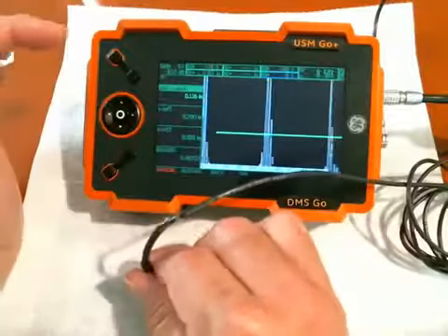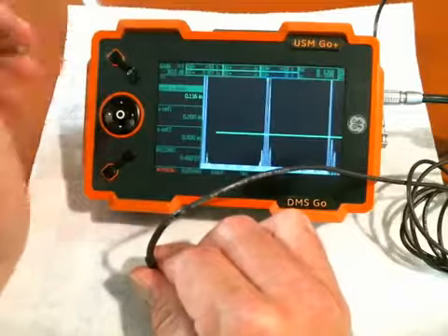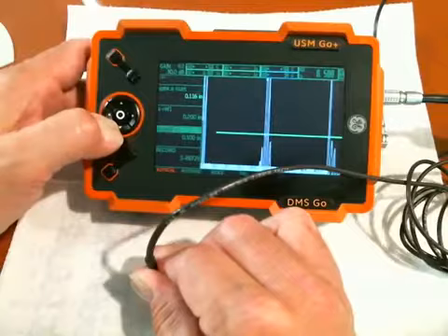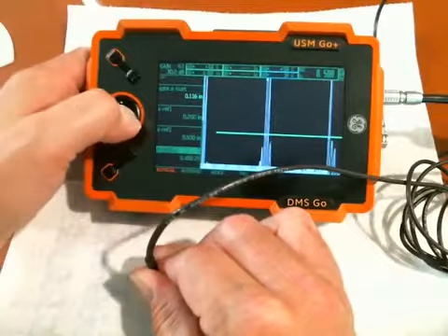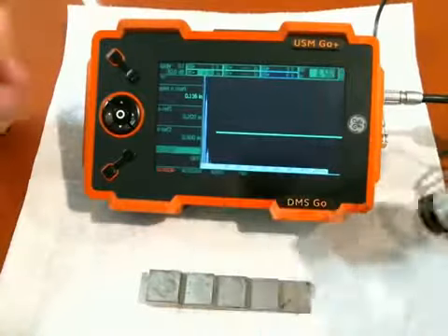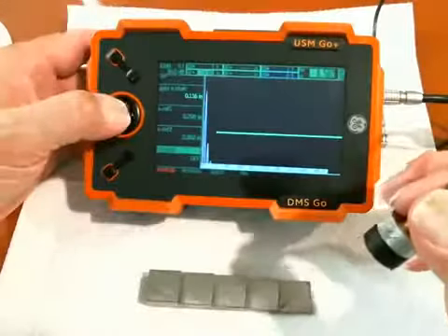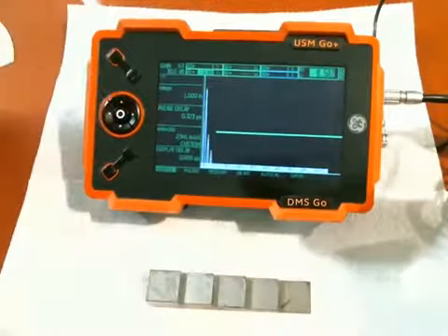So if I needed to move my gate to pick up that 1/2 inch step, I'm already positioned to be able to easily move the gate. In this case, I don't need to move it. There's nothing to interfere. So I come back down to record. I'm on my 1/2 inch block. I go right again. It says AutoCal complete, 0.2341 inches per microsecond. And it told me what the probe delay was too.